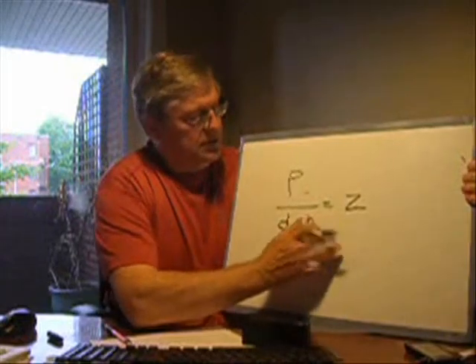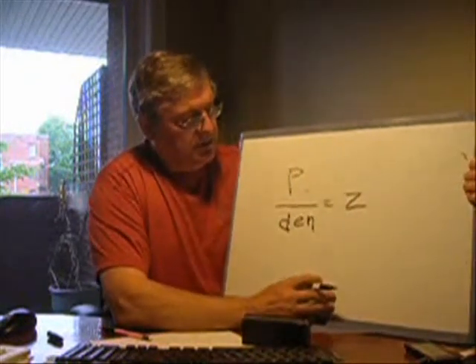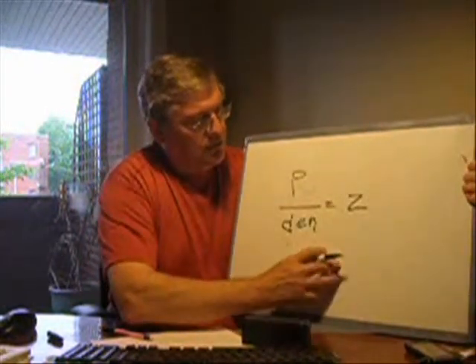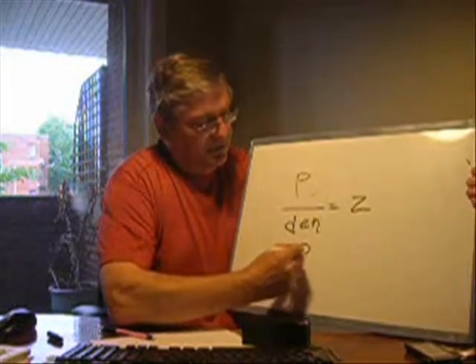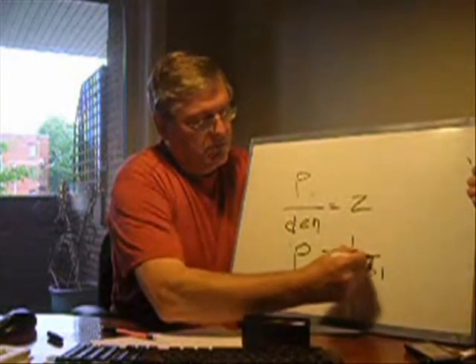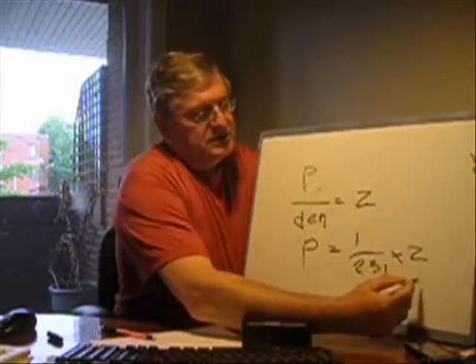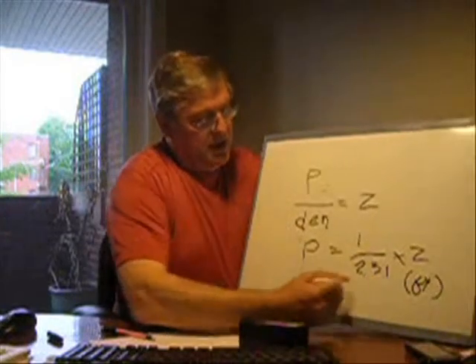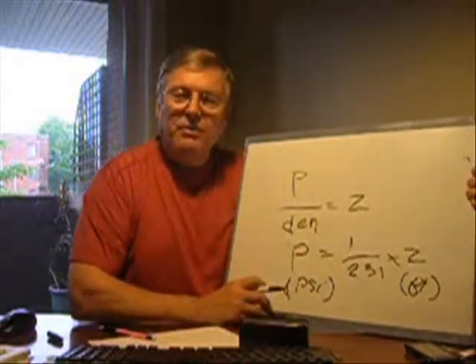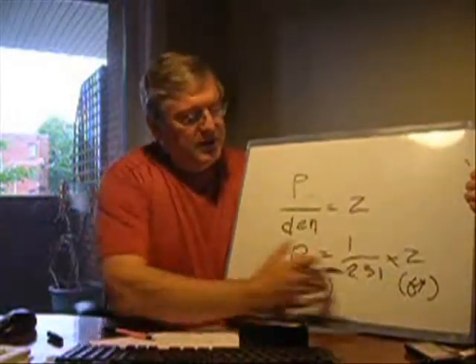For water, getting the units right: if I want pressure in PSI, height in feet, and density in pounds per cubic feet, I find that P equals Z divided by 2.31. So Z is in feet and P is in PSI — a very neat relationship. We can use a pressure gauge in PSI and measure heights in feet with an easy correspondence.